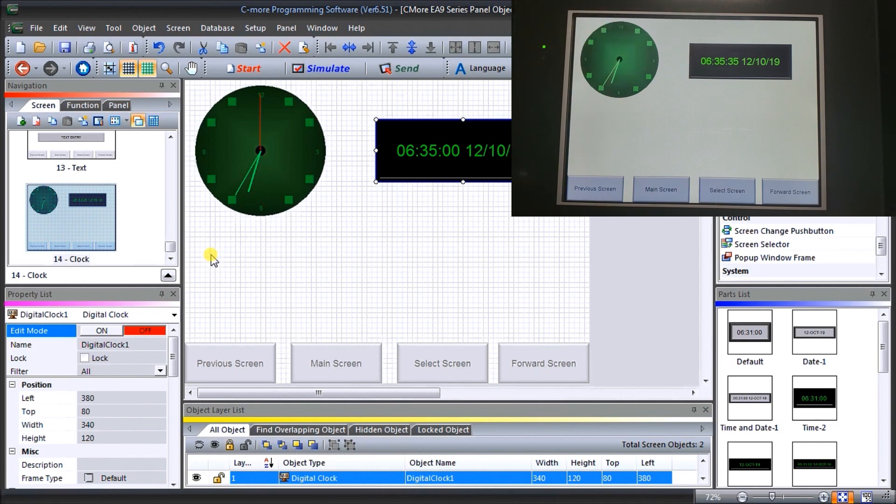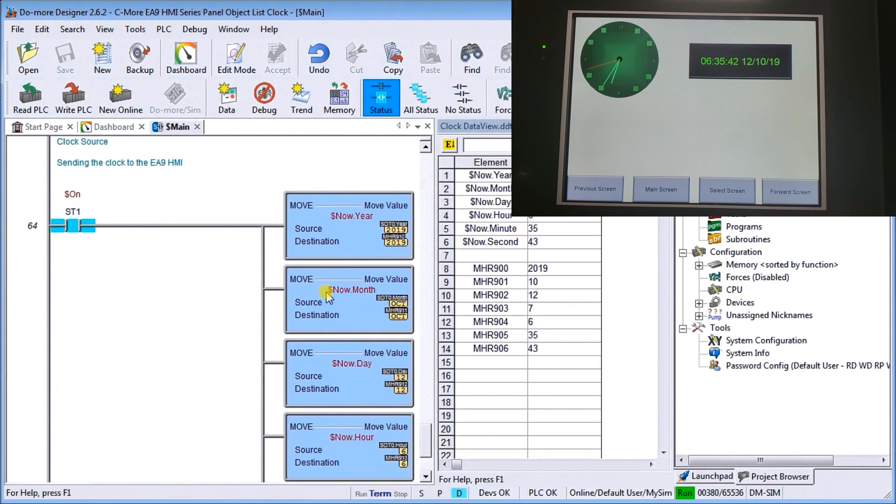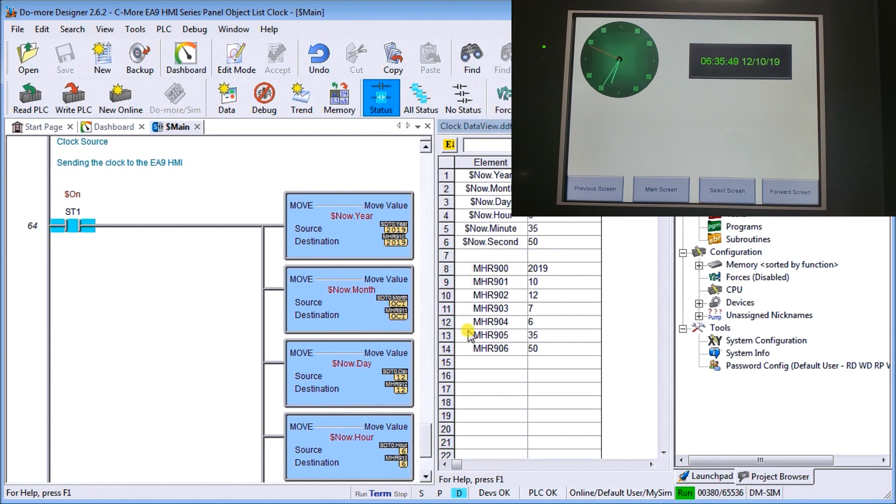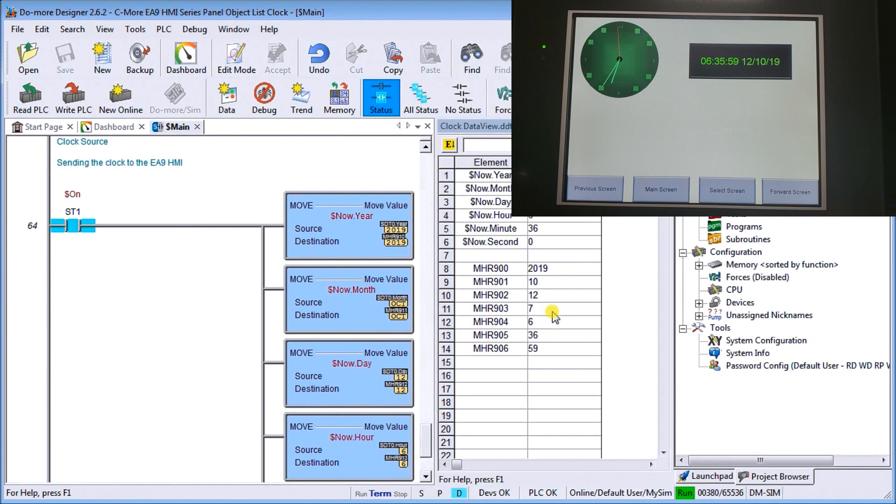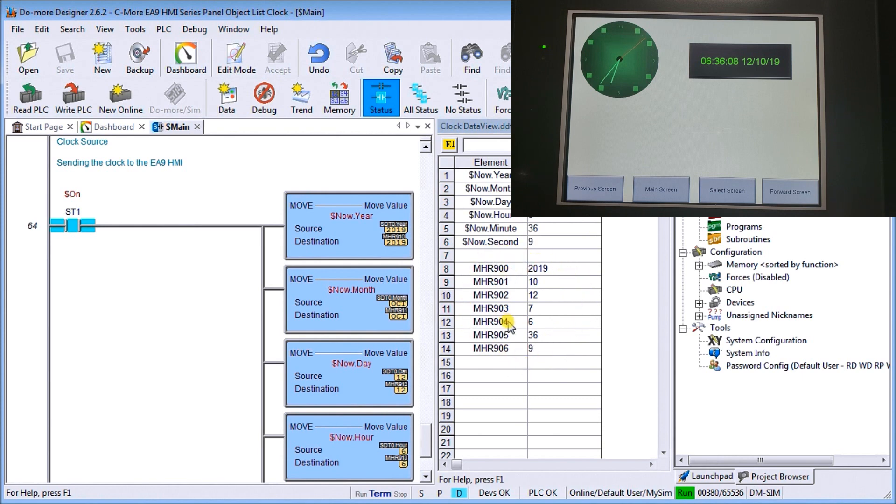If we look at our PLC program, we're using the Do-more Designer. What we did was we said that we're going to write the clock into our MHR holding registers from 900 to 906. So there's my year, month, day, day of the week, hour, minute, second. That's exactly what's happening right now. We can then pick this up and put that into our PLC or use that within our PLC.